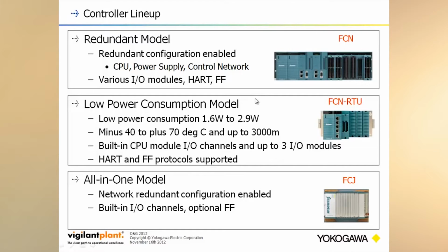Since this one is designed to operate in outdoor situations, it's got a wide operating temperature range of minus 40 degrees to 70 degrees Celsius at up to 3,000 meters. It once again has the built-in I/O in the CPU module. It's actually got a pretty good I/O count, and we'll cover that a little later. It too supports the HART and Foundation Field Bus protocols off the I/O.